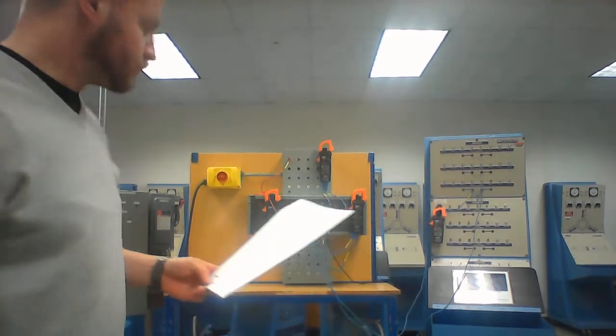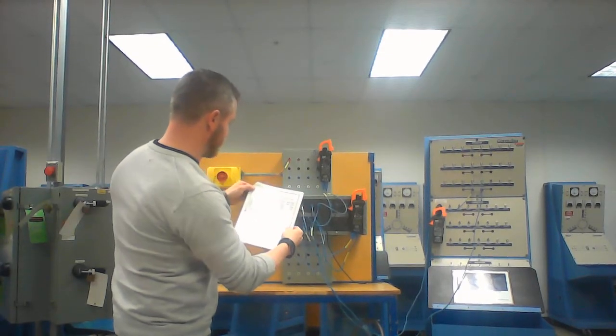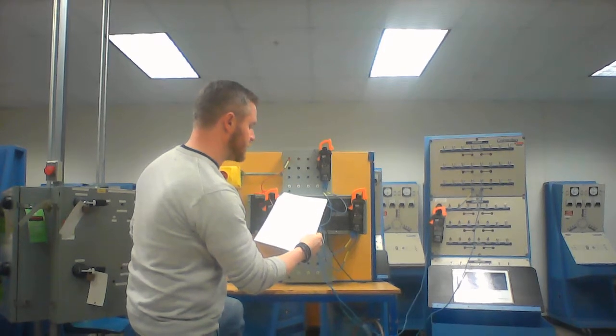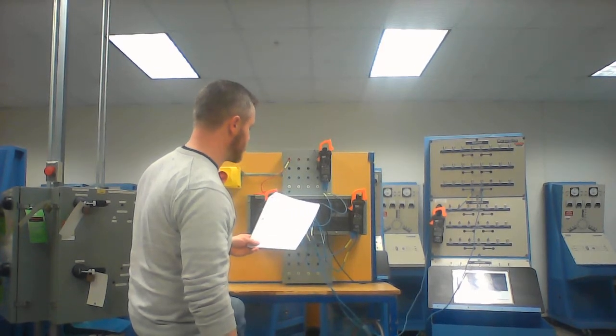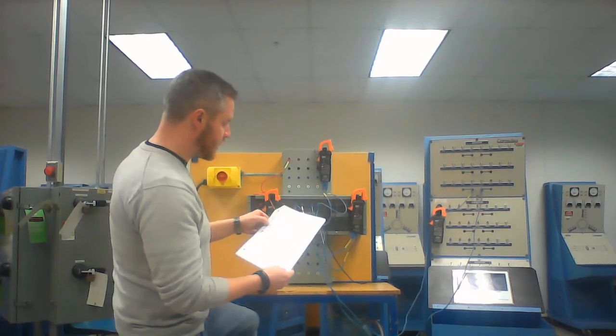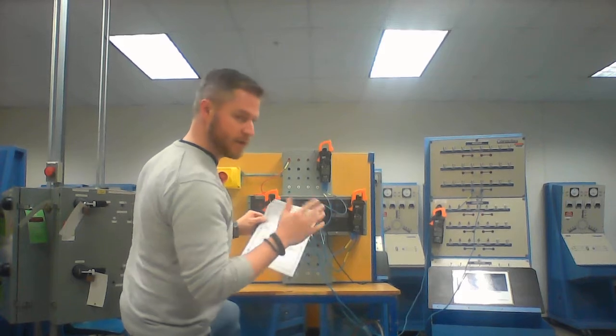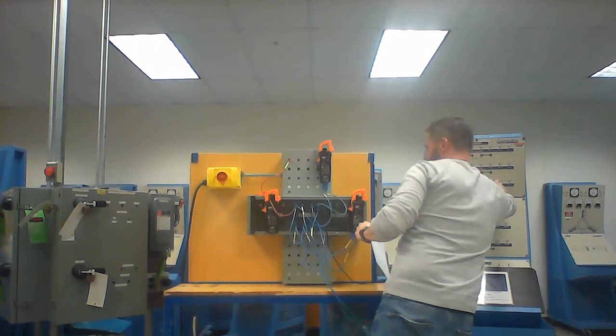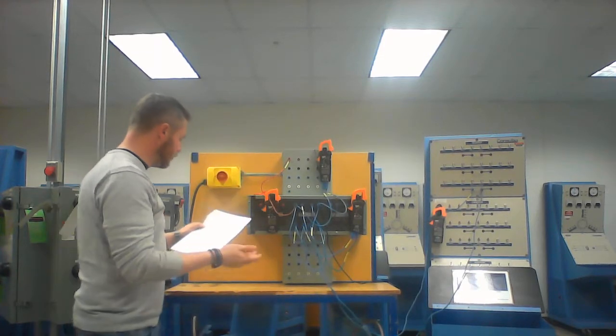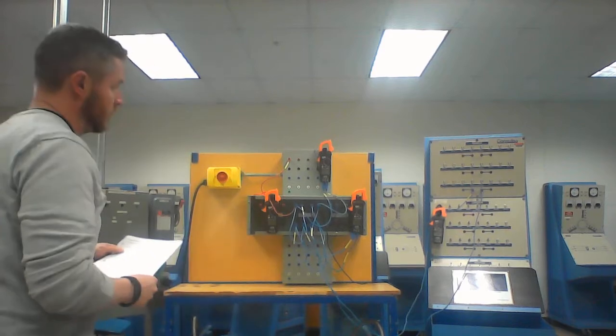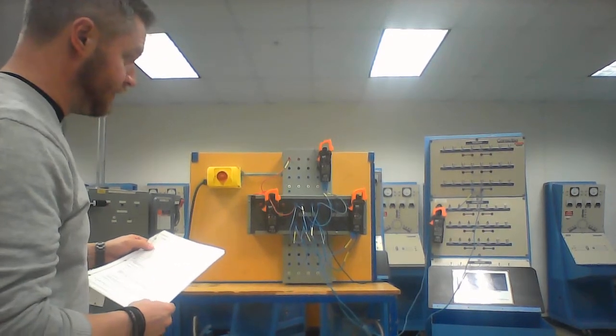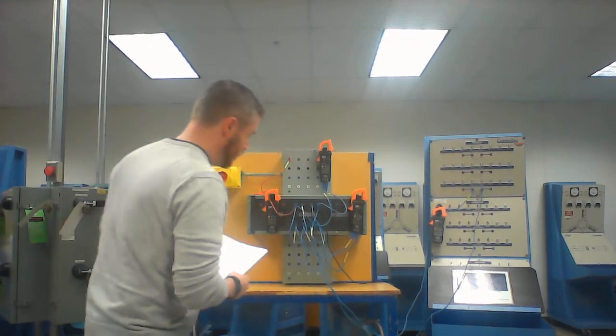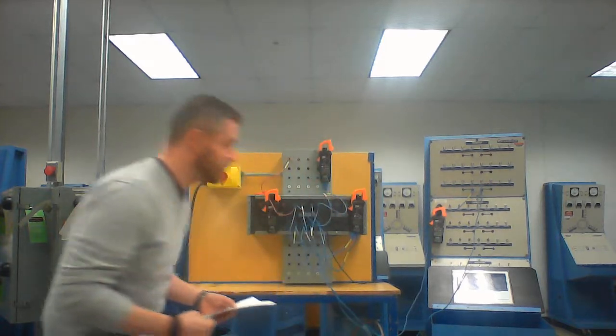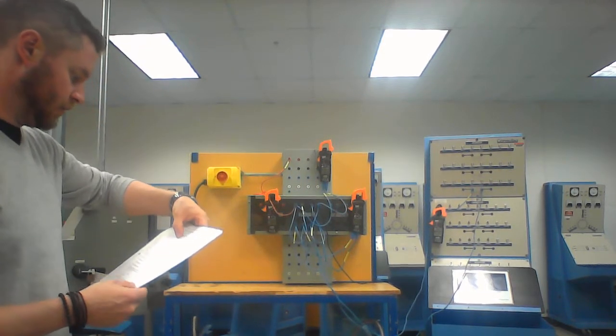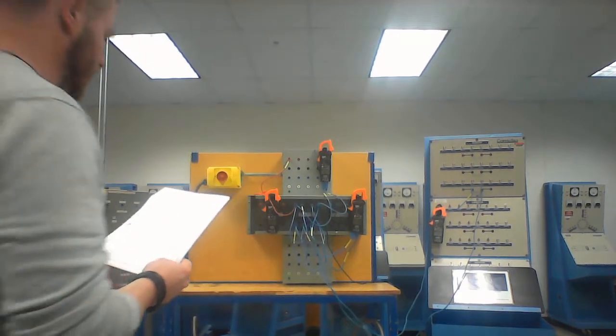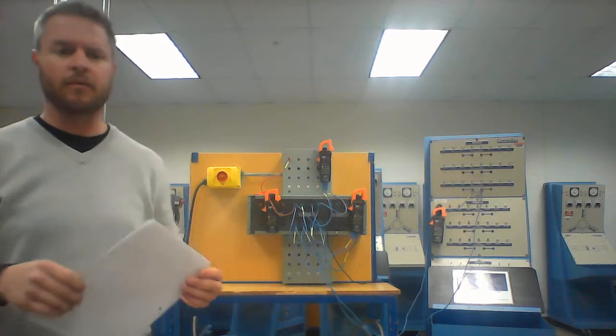Okay, so it says no load in this table here. Step number 11, record your values in the following table for your findings of no load, 220 ohms, 110 ohms, and 73 ohms load. So I'm going to do no load first, and we've kind of done these values already on the first page. So I'll turn off my 220 ohm resistor, and my no load values, my primary voltage, 203.5. So I've dropped a half volt. No load value, secondary voltage, 124.9. We'll do calculated voltage ratios later. Excitation current is going to be the same for all of your loads, and previous to that was about 100 milliamps.